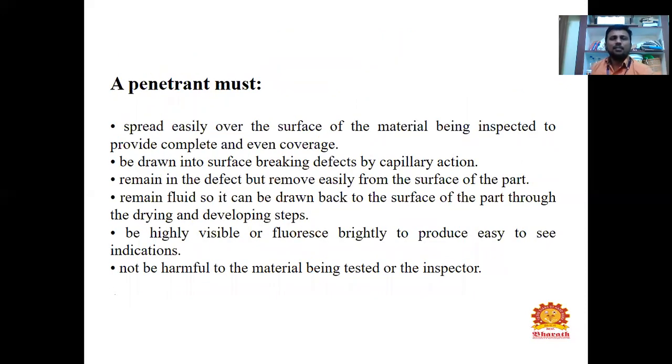Then the penetrant, how is it made? The penetrant must have some qualities. It must spread easily over the surface of the material being inspected to provide complete and even coverage.